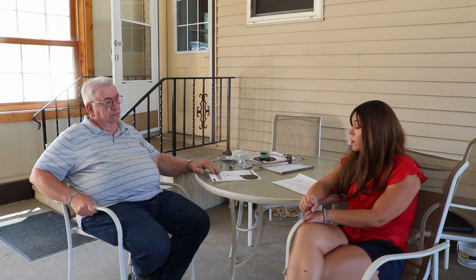Okay. So let's say we have somebody who has a 200,000 BTU unit and the boiler is 175 feet from the home and they are running water to air exchangers. Approximately what size pump would you say? You would need a larger pump. I guess Bell and Gossett or any of the larger pumps that will produce anywhere from 18 to 35 gallons a minute. Wow, 18 to 35 gallons.